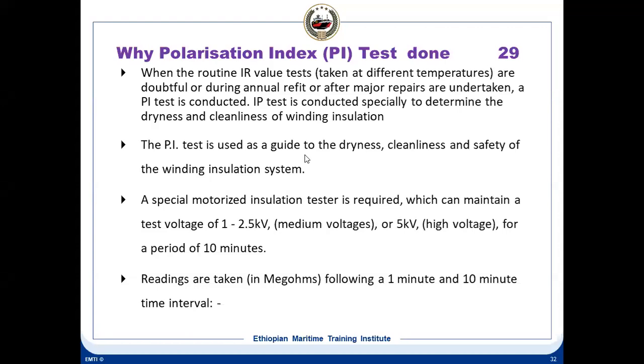So when the routine IR values, like the routine insulation resistance test at different temperatures, are doubtful, or during annual refit, or when major repairs are undertaken. Suppose the generator is in the dry dock lying idle for a long time, then you have to go for this polarization index test. And the PI test is conducted specially to determine the dryness and cleanness of the winding insulation.